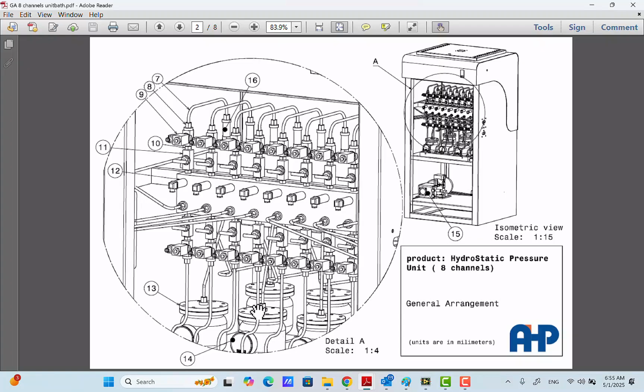As you know, the charge pressure inside an accumulator will be less than the pressures that you will use from that accumulator. Suppose you are using a specific line of the machine for pressures between 10 and 30 bar, or 10 and 25 bar. Then the air pressure inside this accumulator needs to be less than the minimum pressure you're using with that line, meaning less than 10 bar. So for a line between 10 and 30 bar, the accumulator pressure needs to be set below 10 bar. 8, 9, or 7 bar is okay.